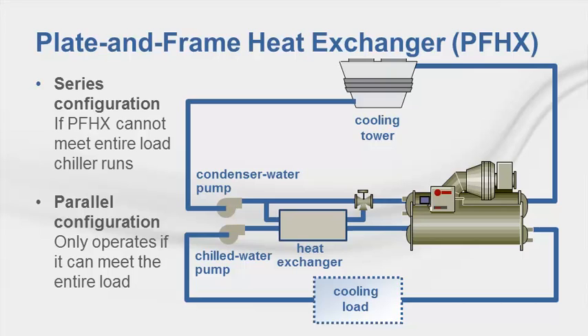This slide shows a simplified depiction of a series-connected heat exchanger. When the heat exchanger is configured in series with the chiller, TRACE first tries to have the heat exchanger meet the entire load. If it can't, the chiller handles the remaining load, also known as integrated operation. When piped in parallel, TRACE 700 assumes non-simultaneous operation — condenser water is routed to either the chiller or the heat exchanger with no mixing. An advantage of a parallel configuration is that the chiller can be isolated for seasonal cleaning and maintenance.